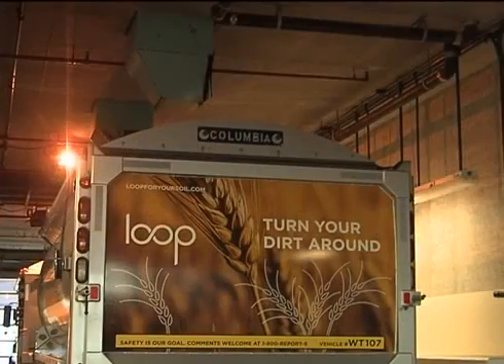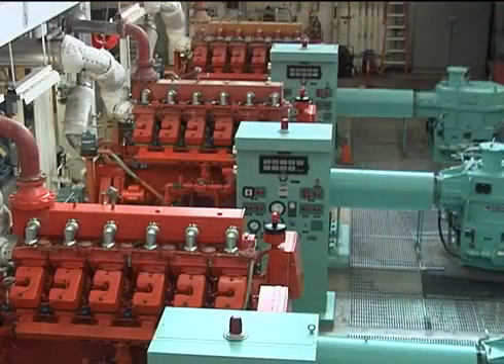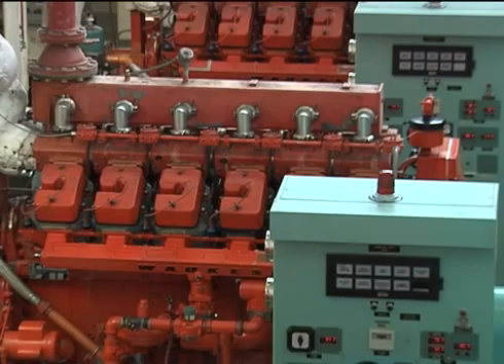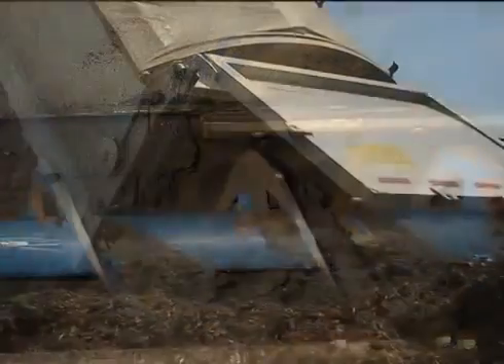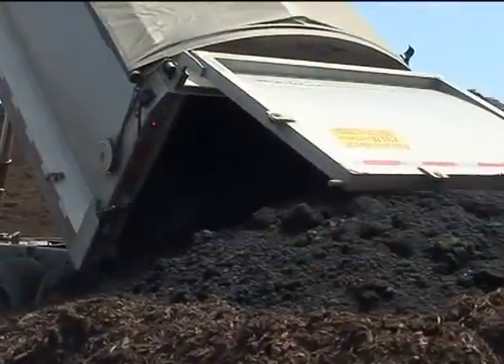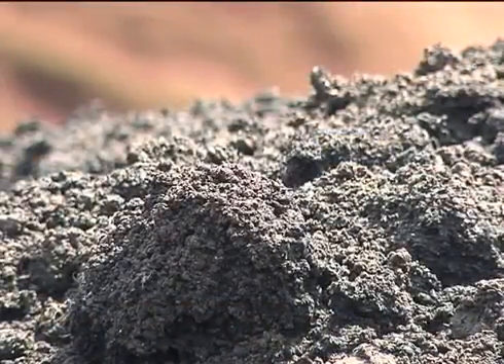Biogas can be recycled as fuel or converted to heat or electricity. West Point has three pumping stations inside the plant. Its influent pumping station utilizes reciprocating engines that burn biogas generated on site by our digesters. The heat energy recovered from these engines is in turn used to heat the plant and to support plant processes. Digested sludge is dewatered with high-speed centrifuges to produce biosolids for farm, forest, and garden soils. West Point recycles four to five truckloads, or about 120 tons, of biosolids every day.